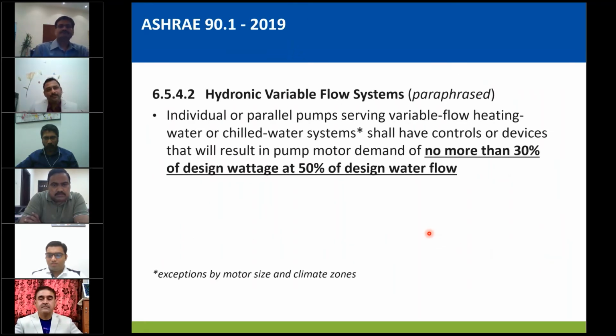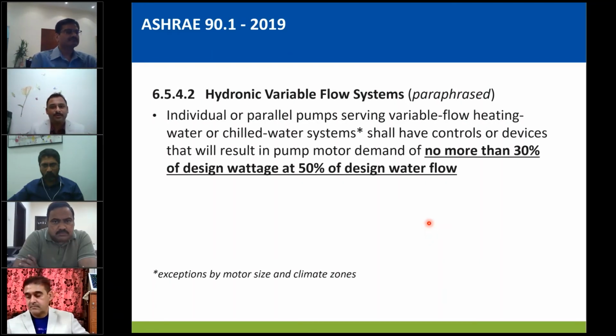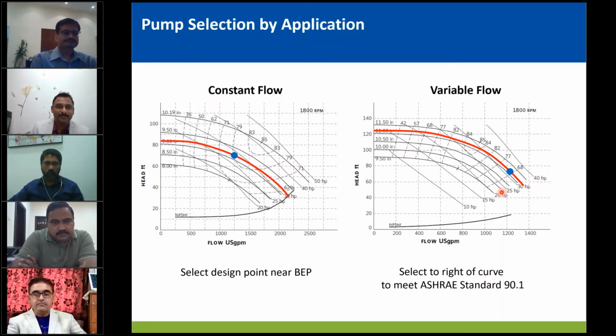Now coming to variable flow systems. ASHRAE 90.1 specifies that any pump should consume only 30% energy at 50% flow. That means at part load, it should not spend more than 30% energy. 70% savings to be achieved at part load. Now this is for variable flow systems, and this cannot be achieved if we practice the traditional way of selecting the pumps. That takes us to selecting the pumps for the specific application.